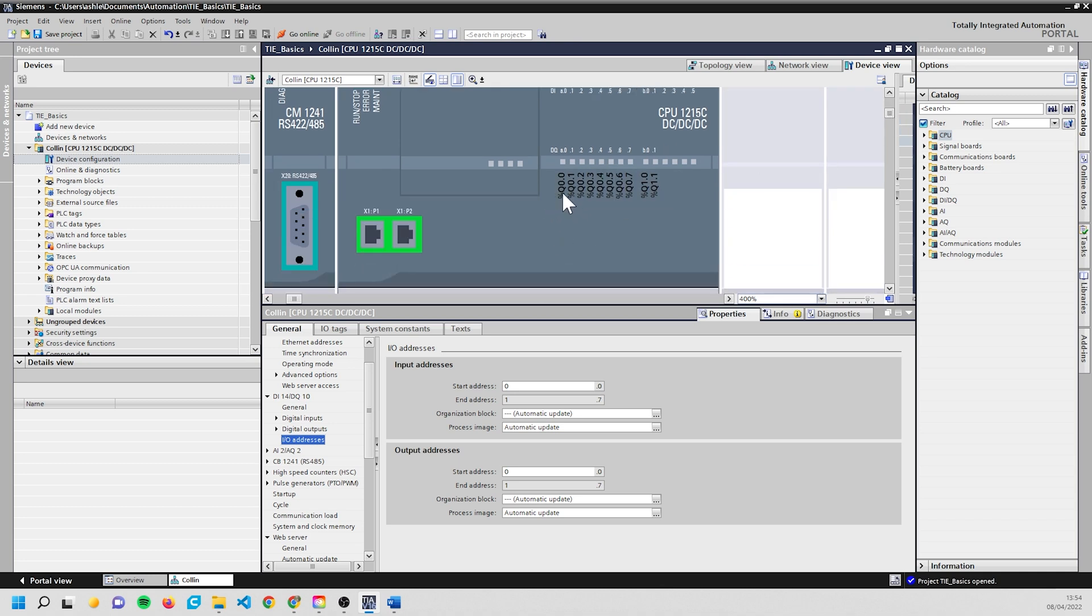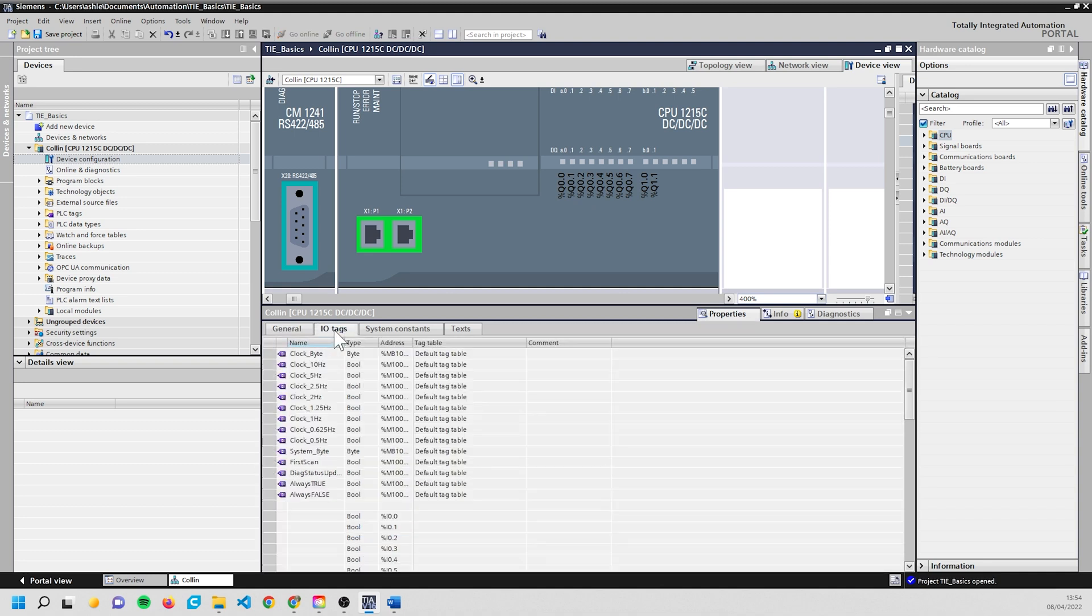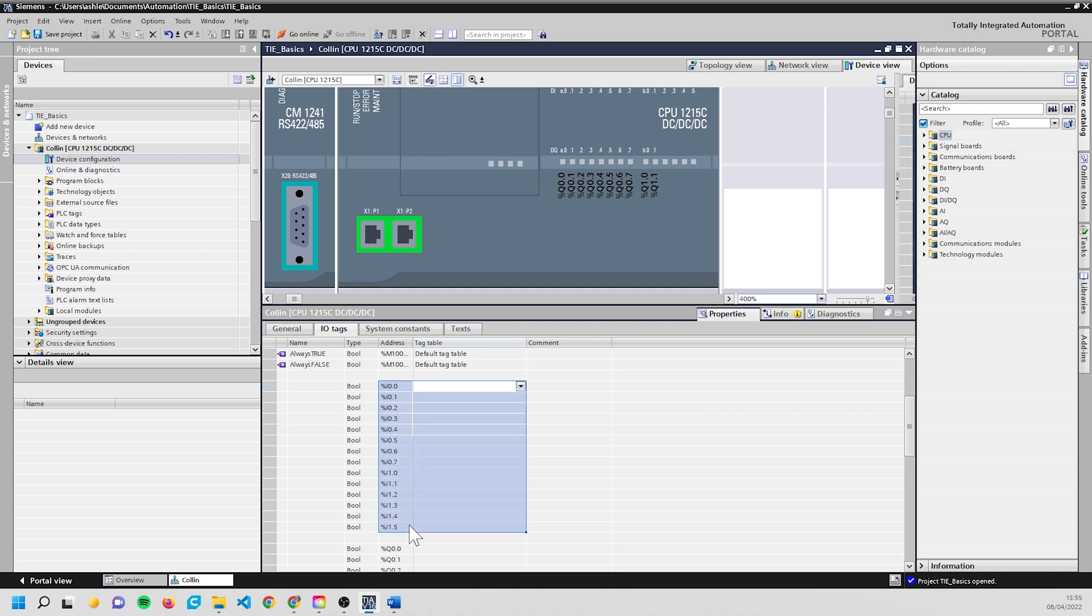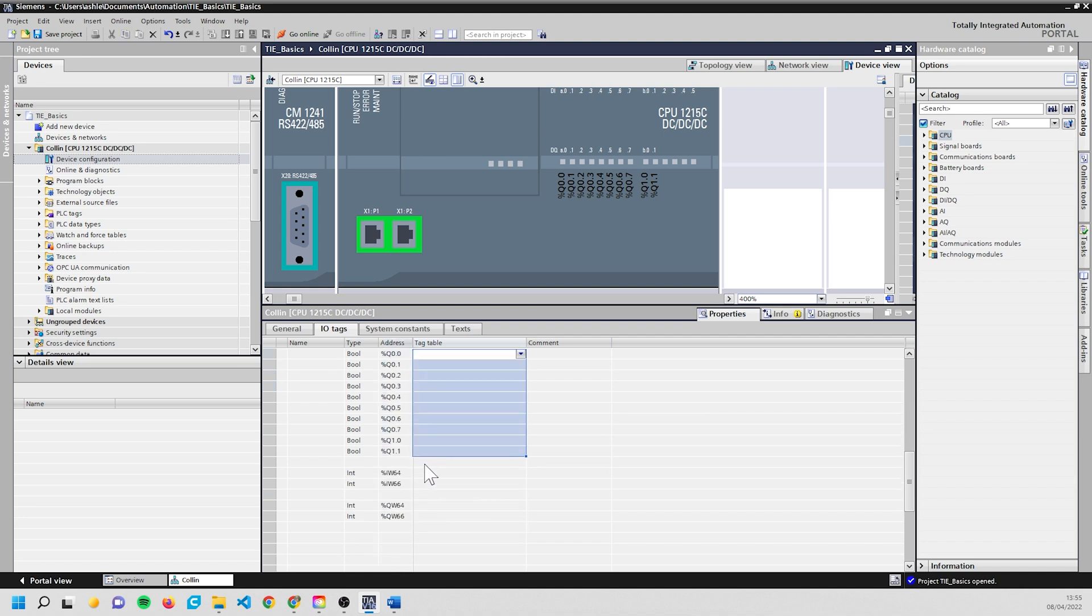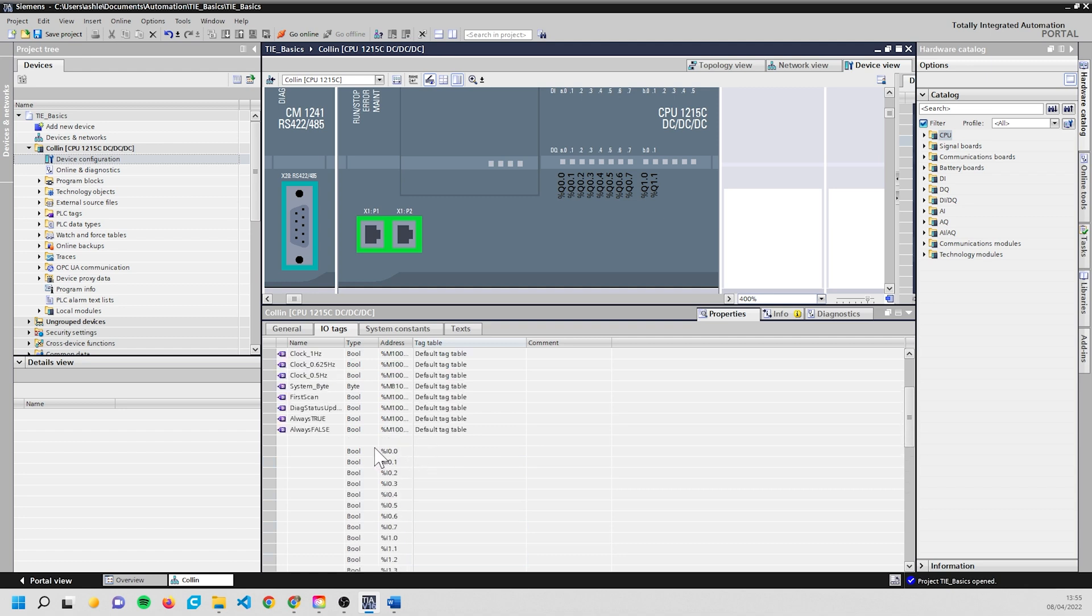So now our inputs are starting at I0.0 and going up, and our outputs are starting at Q0.0 and going up. Q is shorthand for output, so if you see DQ, just see it as digital out. What we're also going to do is have a quick look in the I/O tags. This is from a previous video where we initiated the clock memory and system memory. We've got these in the tag table already and you can see down here we already have all of our inputs, all of our outputs, and on the 1215C we've got a couple of analog ins and a couple of analog outs.